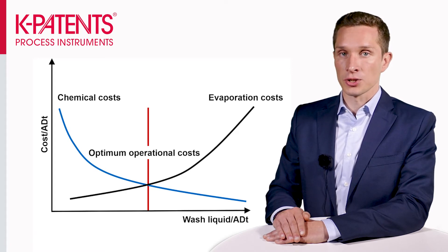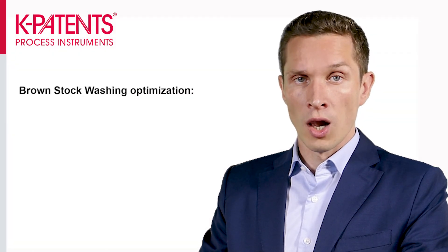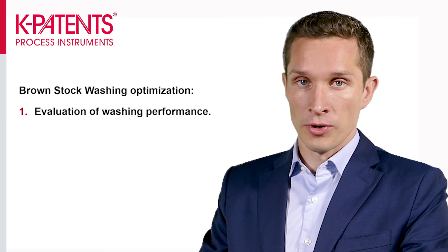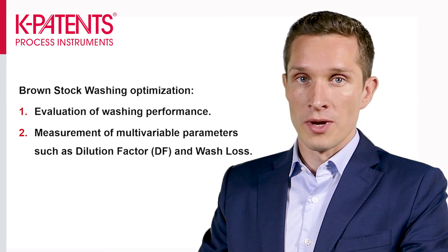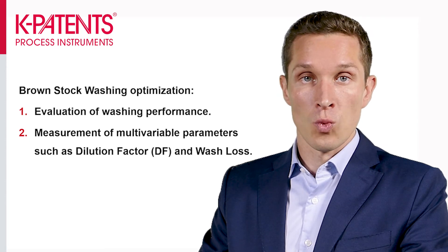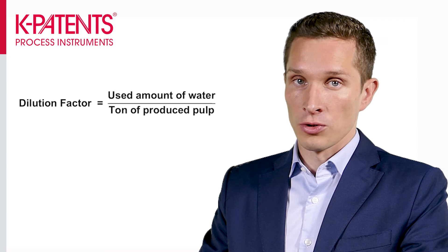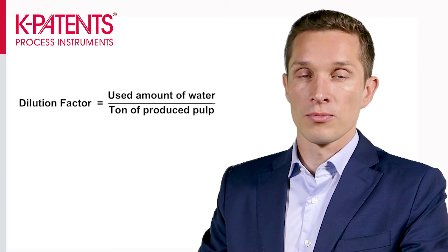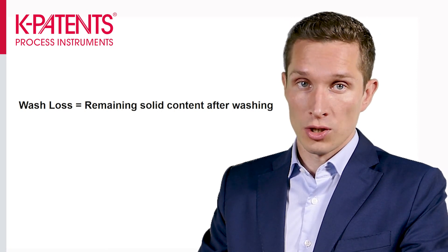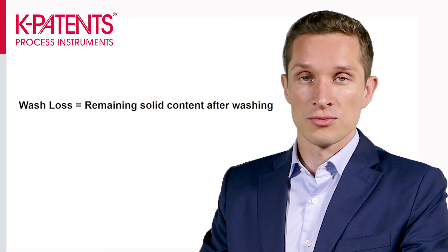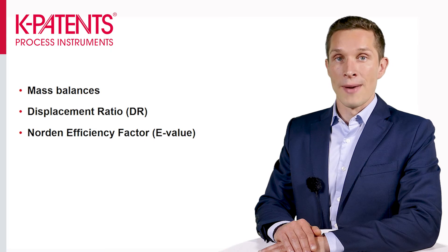By optimizing the line operation, the mill guarantees the best economic and environmental performance. So how is brown stock washing optimized? First we need to measure and evaluate the washing performance. This is done by using multi-variable parameters. The two principal parameters to measure are called dilution factor and wash loss. The dilution factor indicates the used water amount per ton of pulp. Wash loss is the dissolved material or dissolved solids which were not removed in the washing but instead continued to the bleaching stage.